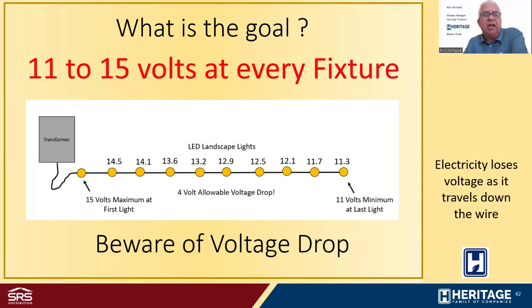So you can see in this example, we have 15 volts to the first light, 14.5 at the second, 13.6 at the fourth, 12.5 about a little more than halfway down, and that last fixture on our run has 11.3. So because we have at least 11 volts at that last fixture, this circuit is fine. No more than 15 at the first light and at least 11 at the last light. So when you install your system, you want to take your voltmeter and check the last fixture on that wiring run or that wiring circuit to make sure it has at least 11 volts.